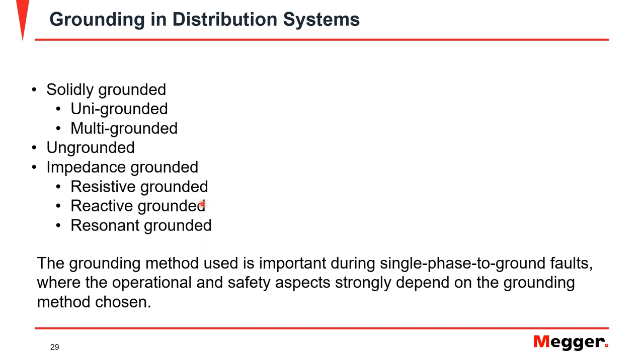Regarding grounding, distribution systems can use solidly grounded systems (most common in North America, including Mexico, the United States, and Canada), ungrounded systems, or impedance grounded systems (resistive, reactive, or resonant, more common in Europe). It is very important to know the grounding method used, as it has a large effect during single-phase-to-ground faults, and you must know your grounding system to properly design and test your distribution protection system.